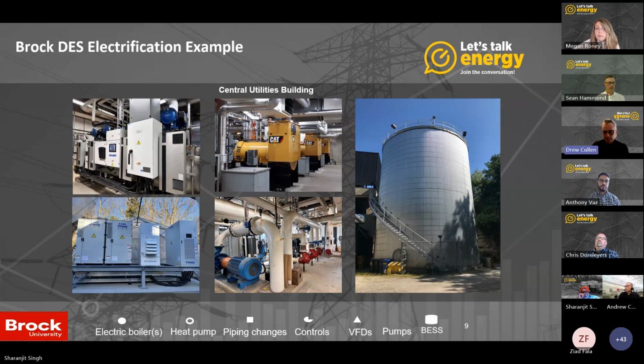How we achieved these results was by utilizing our electric boilers on our DES system, our district energy system. Brock, back in 1964, was a fully electric campus and used these electric boilers as standalone boilers for heating. In the 1980s, when natural gas became more mainstream for heating, the electric boilers weren't being used anymore. However, we've revitalized them and brought them back into play, and now we're using them to support the district loop with heating, supplying the BTUs needed through direct connections from the electric boiler systems in these mechanical rooms into the district loop.